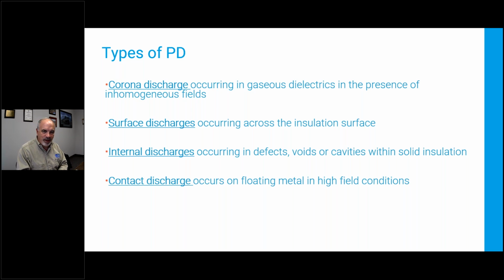Surface discharge is a little different in that it's still at the air insulation border, but that current pulse travels across the surface of the insulation. It doesn't go out into the air much. It might go a little bit, but it's mainly traveling on the surface of the insulation. This is the most common destructive form of partial discharge. You know, with Corona, we're destroying the air molecules, but new air molecules take their place, so it doesn't build up. It doesn't get any worse. It's there. It's annoying. It creates radio waves. It creates ground-level ozone, but it doesn't create catastrophic failure typically. Surface discharge, I've got some defect, causes the discharge, but the act of the discharge damages the insulation even further, which makes it cascade and eventually fail.